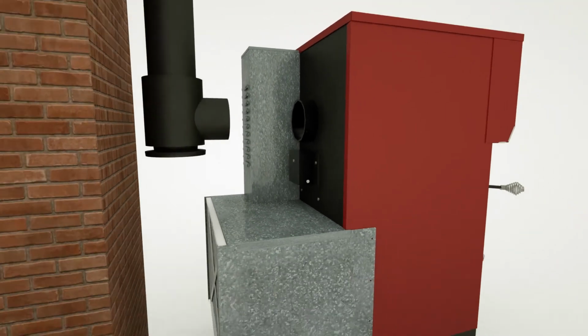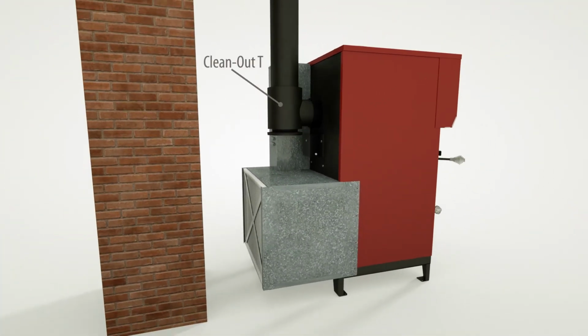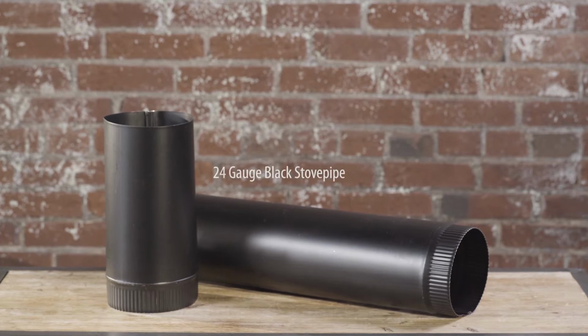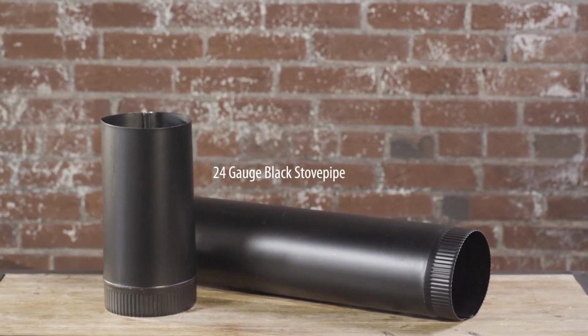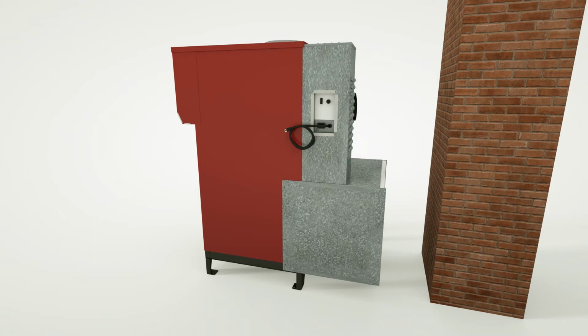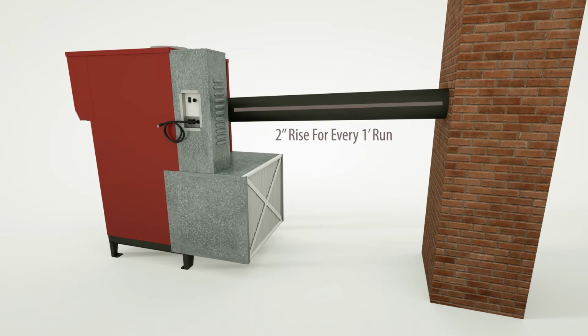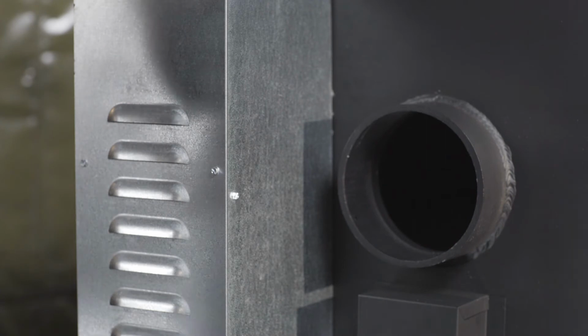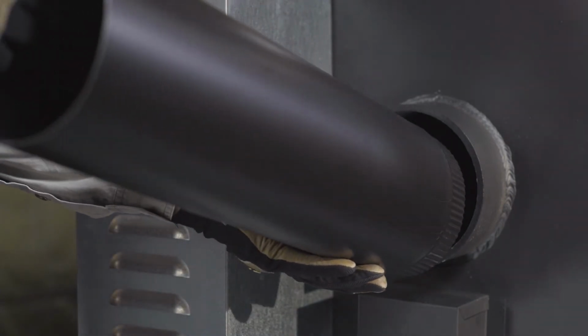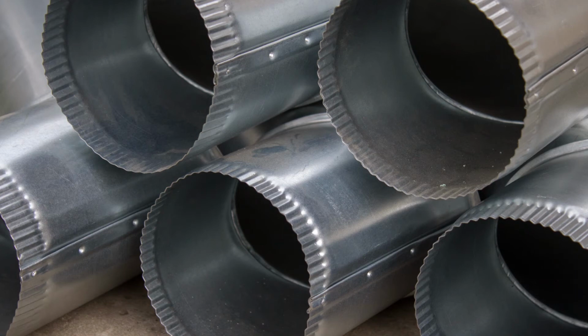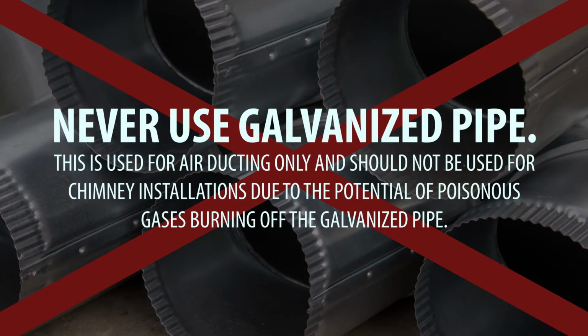If installing Class A chimney pipe, there must be a cleanout tee attached. The pipe to connect the furnace to the chimney should be a minimum of 24-gauge black stovepipe. It is important to remember, on a horizontal run, chimney pipe must have a 2-inch rise for every 1 foot of run. It is critical to ensure proper clearances to the stovepipe. Connecting sections must be installed with the crimped end down, towards the furnace. Never use galvanized pipe. This is used for air ducting only and should not be used for chimney installations due to the potential of poisonous gases burning off the galvanized pipe.